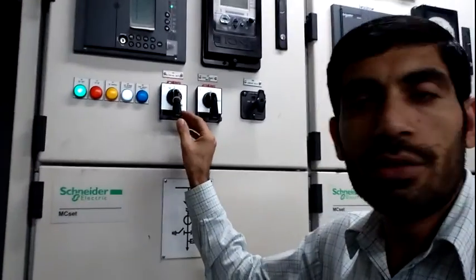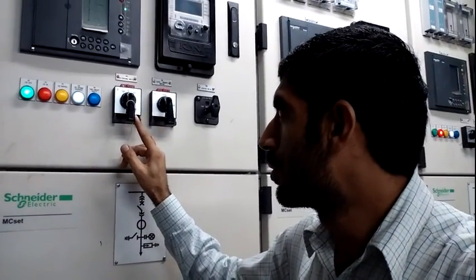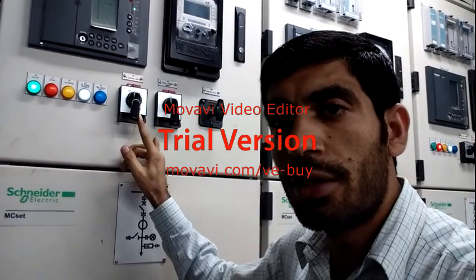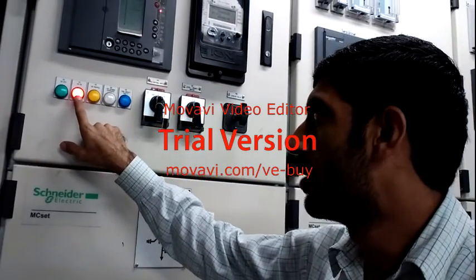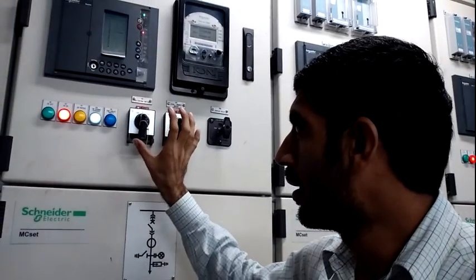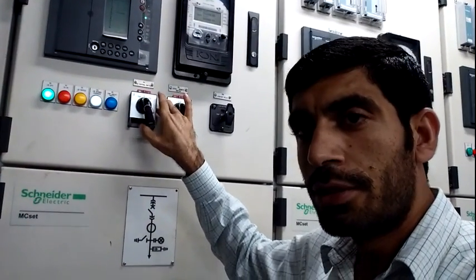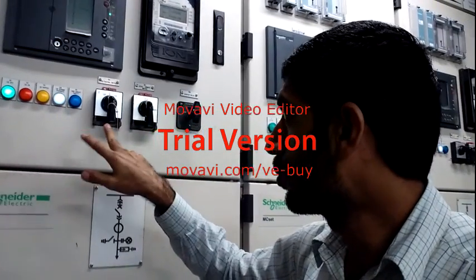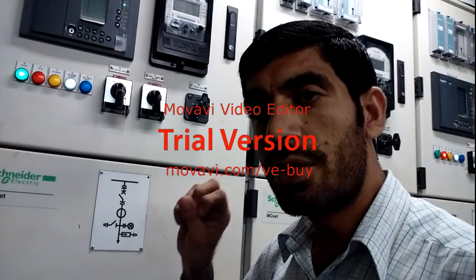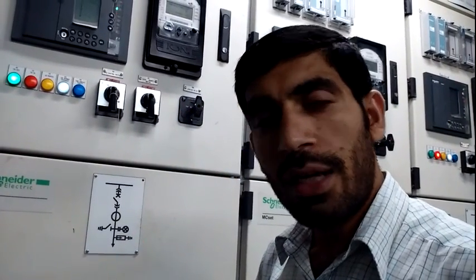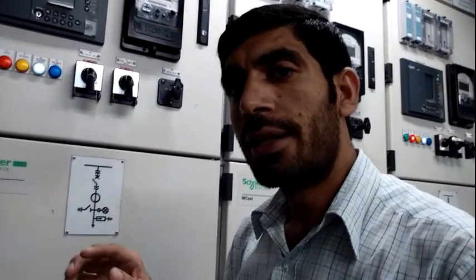I will try to close the breaker through the control switch. When I push the close position, this breaker will be closed. You can see here, the red indication is coming. That means my breaker is closed, and the breaker also shows the charge indication. When I push the trip position, this breaker will be open and both indications come, one for the breaker and one for the charge. So this is for breaker closing. If my switch is closed, I cannot close the breaker here. When I put the switch in open condition, I can close the breaker.